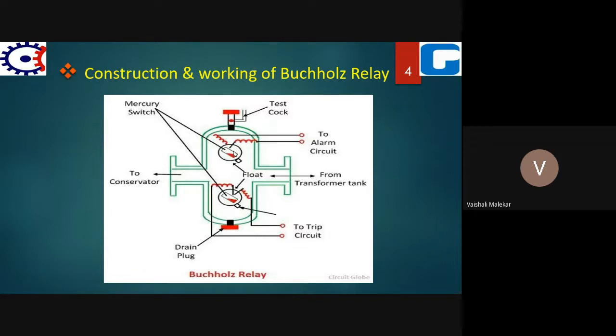Now these gas bubbles move towards the conservator through the pipeline. These gas bubbles get collected in the relay chamber and displace the oil. As they get collected at the top side, the oil gets displaced. This displacement of oil will be equivalent to the volume of gases collected. Whatever volume of gases is collected at the top side, that much volume of oil gets displaced. Now this displacement of oil tilts the hinge float at the top side.